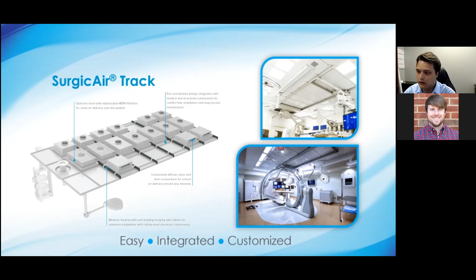How we do this is by providing framing members that integrate directly to that ceiling level unistrut with prefabricated hanging tabs. What's unique about this is it allows you to hang that framing directly off the unistrut at a predetermined height, so it can't be accidentally hung too low or too high and get in the way of the medical equipment, causing another conflict. It's easy to install in that it just snaps and sits on top, and it can be scooted around and adjusted.